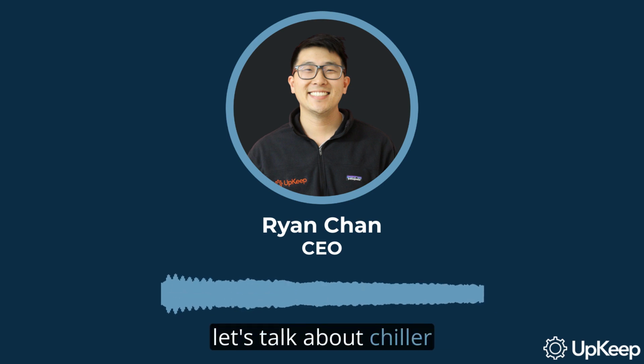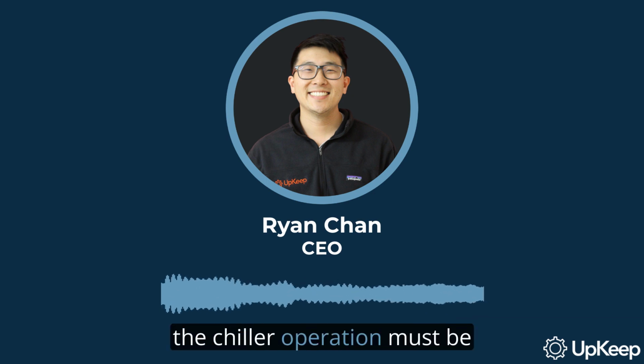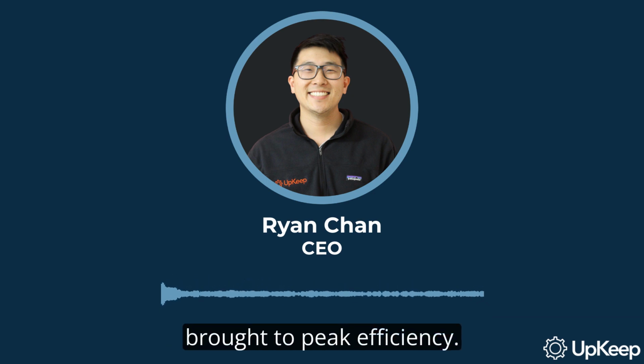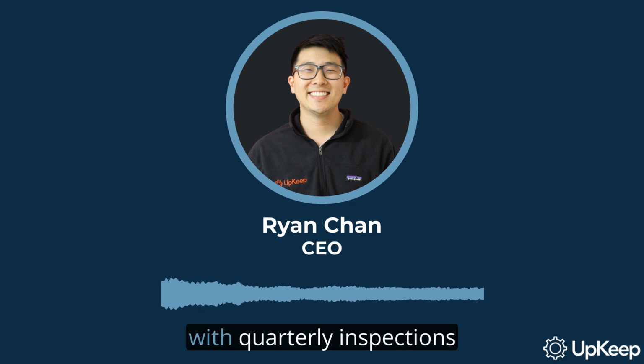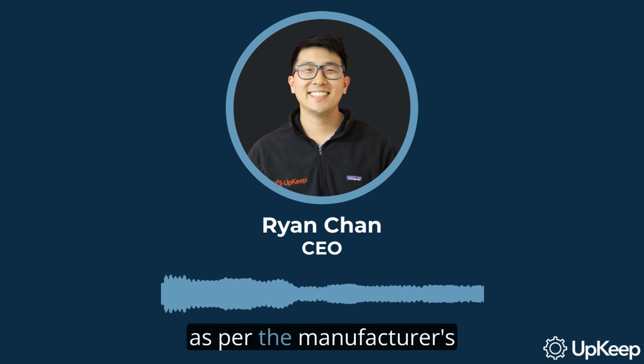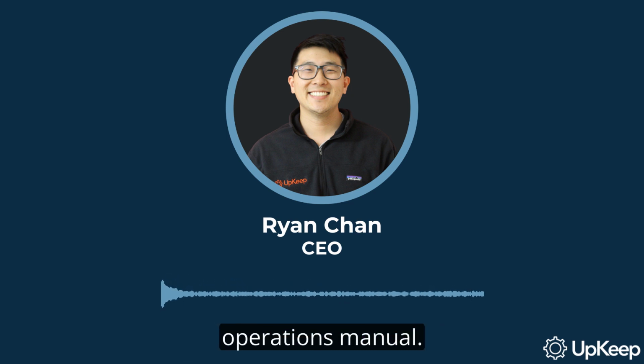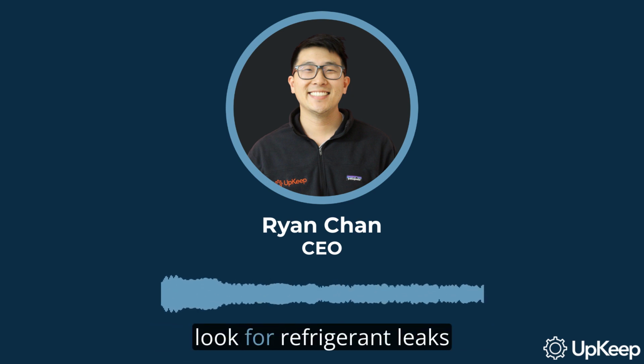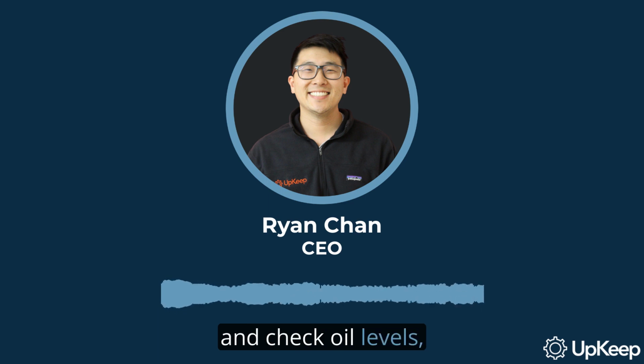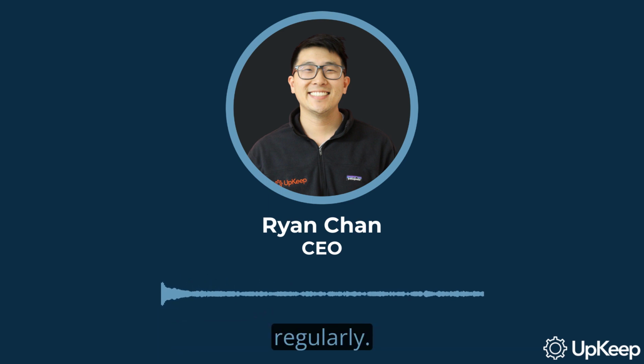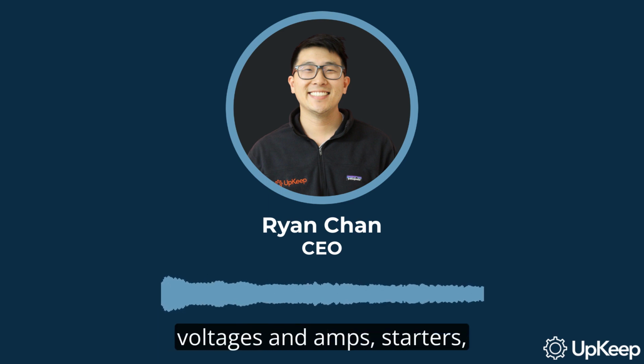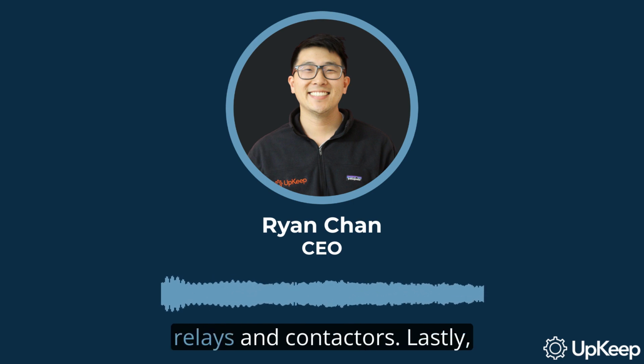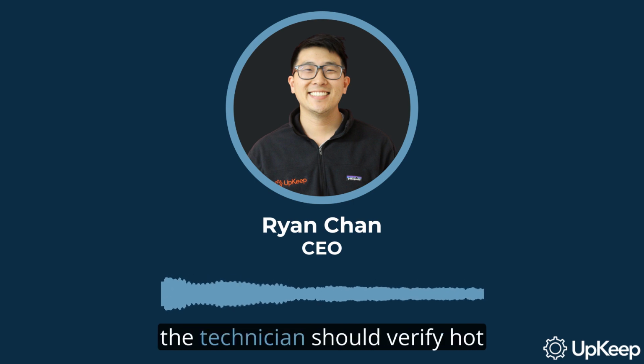Now let's talk about chiller maintenance, which is a two-part process. First, the chiller operation must be brought to peak efficiency. Then, it must be kept at that level. Basic maintenance should start with quarterly inspections, as per the manufacturer's operations manual. Maintenance technicians should look for refrigerant leaks and check oil levels, pressures, and temperatures regularly. They should also check motor voltages and amps, starters, relays, and contactors. Lastly, the technician should verify hot gas and unloader operations.